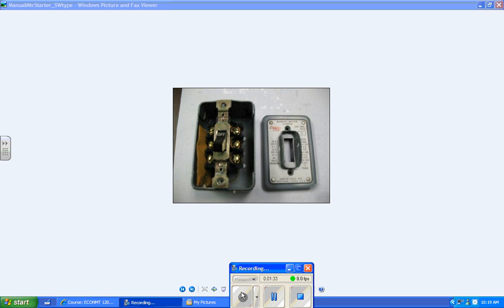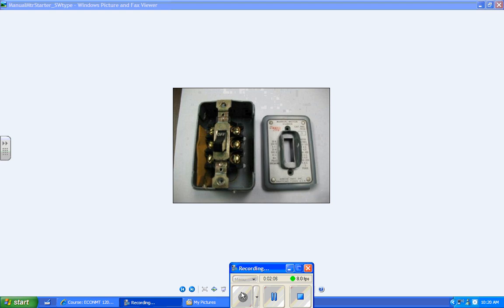If you look at page 28 in your IMC, you'll find that there are two schematic drawings for a two-pole manual motor starter. One of them has one power contact and one has two. They're both single phase, but single phase can be 110 volts only, or it can be 120 volts phase A and 120 volts phase B, or what we call single phase 240 volts, which is two hot circuits. The second drawing, Figure 3-3, is a ladder diagram of a manual motor starter for a 230 volt motor. For quiz purposes you must be able to draw either one of those drawings from memory.